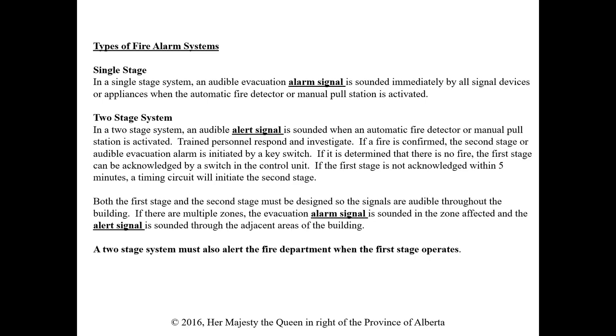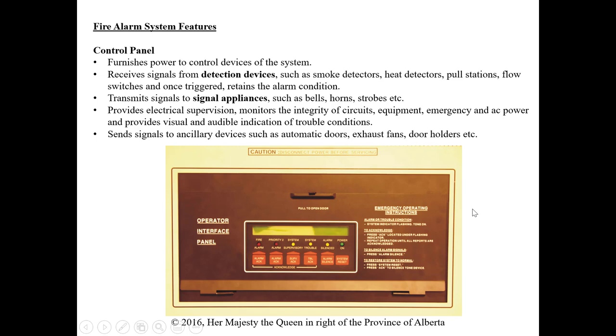Both the first and second stages must be designed so signals are audible throughout the building. In a multi-zone system, the evacuation alarm sounds in the affected zone and the alert signal sounds in adjacent areas, so nearby occupants know there's a fire and can potentially evacuate as well. A two-stage system must also alert the fire department when the first stage operates — they'll call the business to confirm whether it's a real alarm.